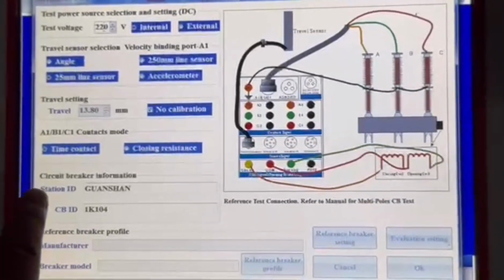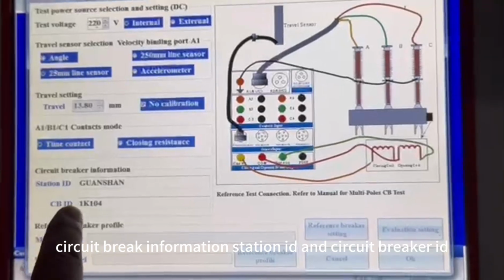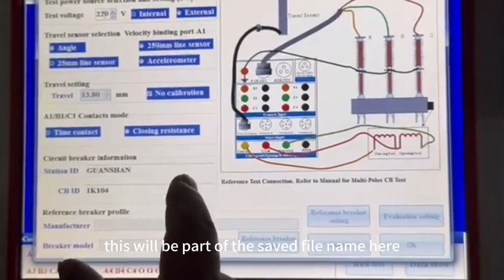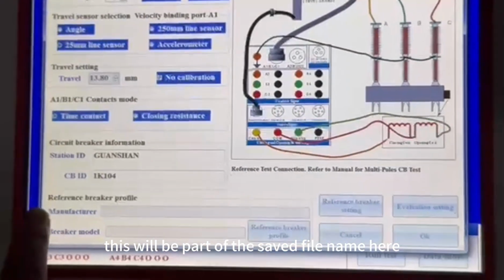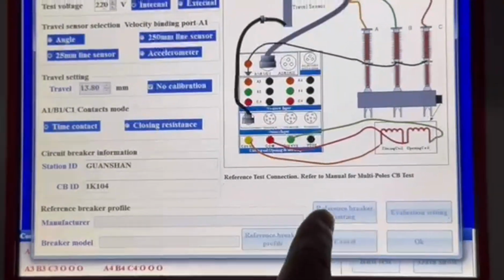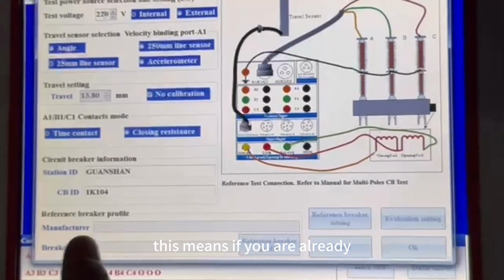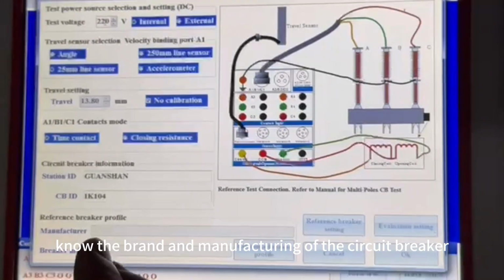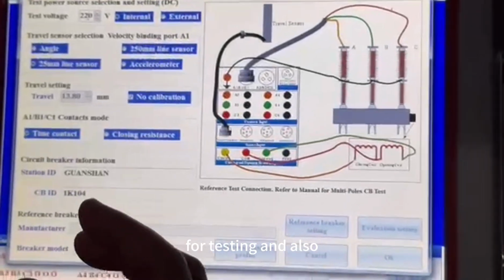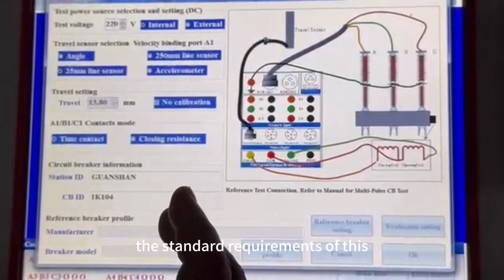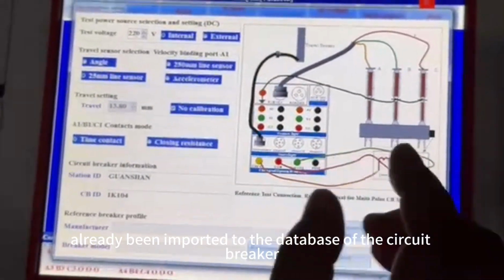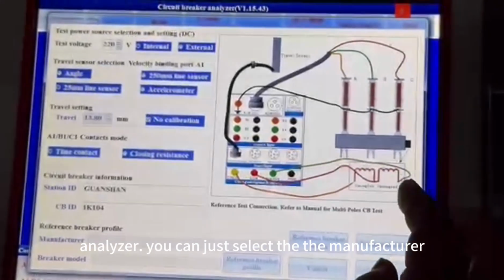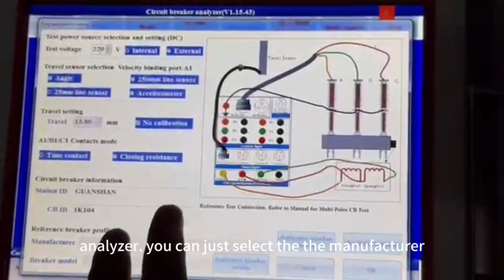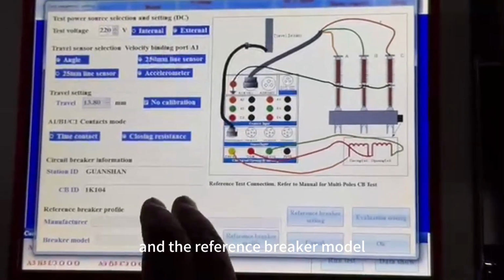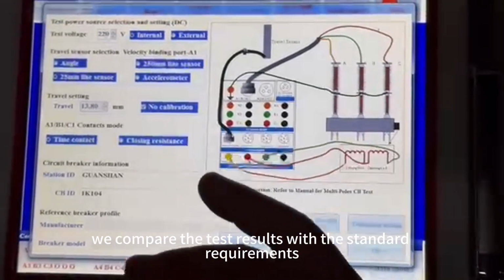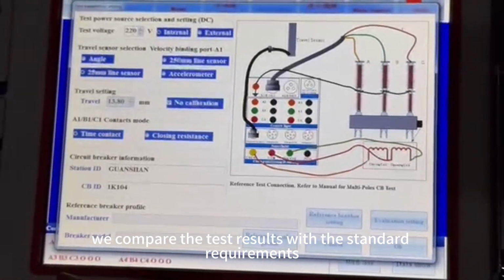And here, circuit breaker information, station ID and circuit breaker ID. This will be part of the saved file name. Here, reference breaker profile. This means if you already know the brand and the manufacturing of the circuit breaker for testing, and also the standard requirements of this circuit breaker have already been imported to the database of the circuit breaker analyzer, you can just select the manufacturer and the reference breaker model. Then the analyzer will compare the test results with the standard requirements.